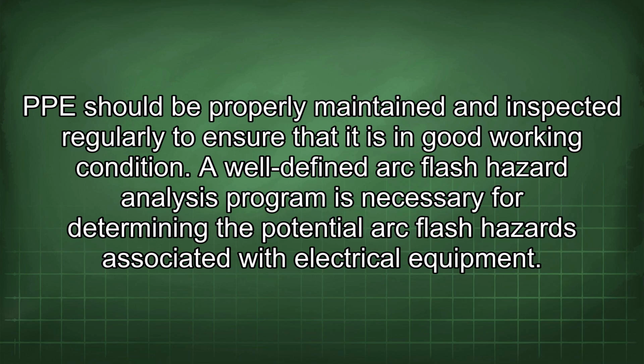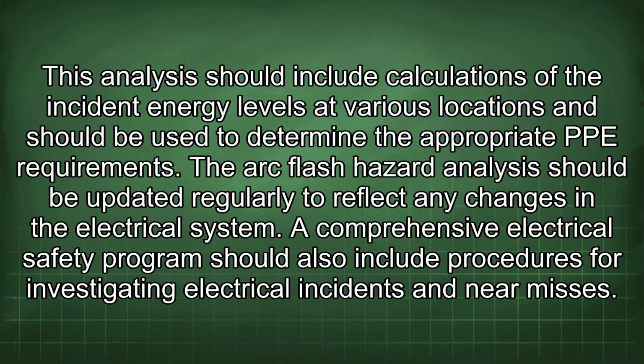A well-defined arc flash hazard analysis program is necessary for determining the potential arc flash hazards associated with electrical equipment. This analysis should include calculations of the incident energy levels at various locations and should be used to determine the appropriate PPE requirements. The arc flash hazard analysis should be updated regularly to reflect any changes in the electrical system.